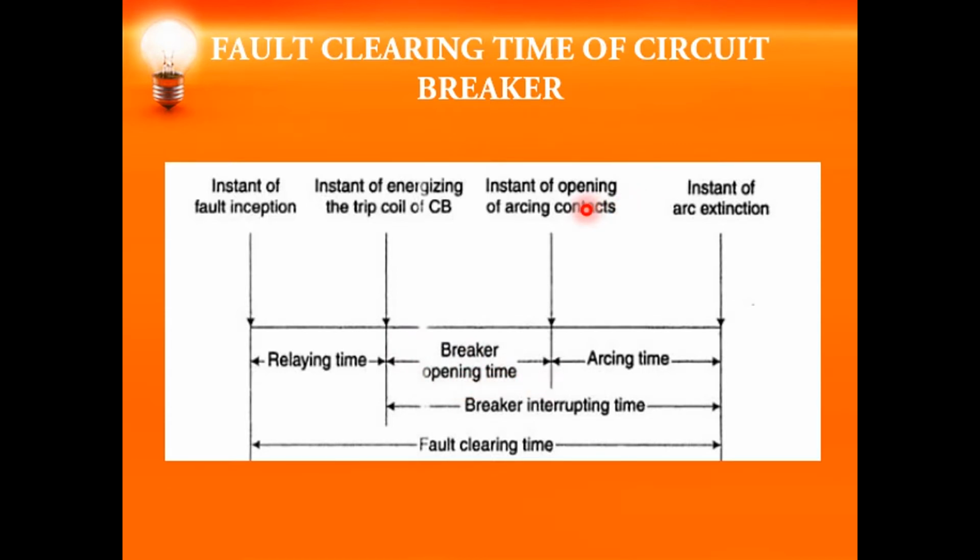Once the moving contact starts separating, the arc is formed and the insulating medium present there has to quench the arc. The time from when the arc is formed until the arc has finally quenched is called the arcing time. So our fault clearing time is from the instant the fault is sensed to the instant at which the arc has quenched. That total time is called the fault clearing time.